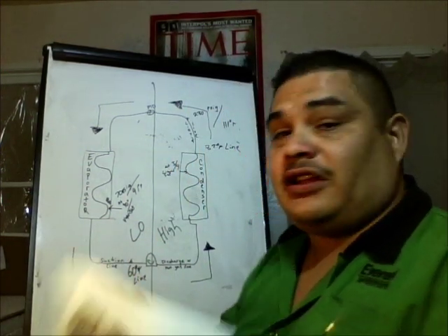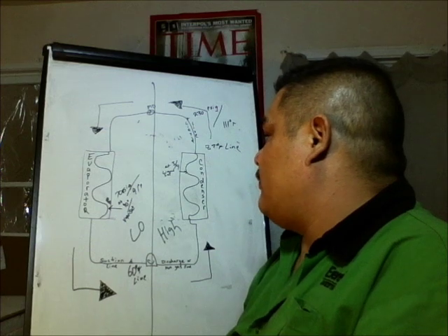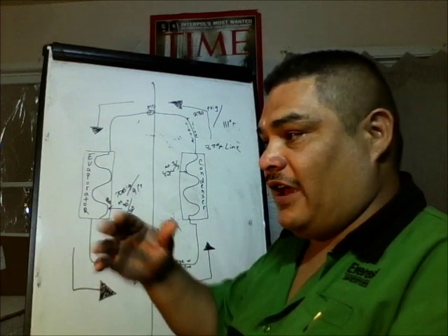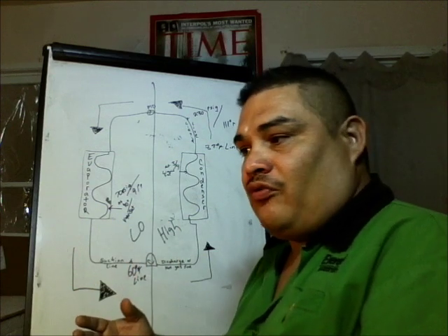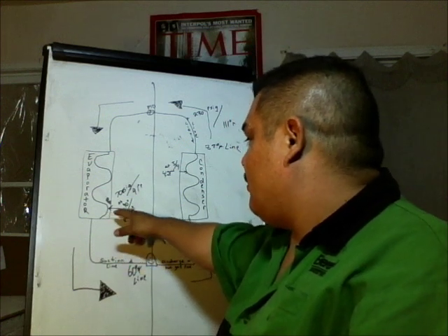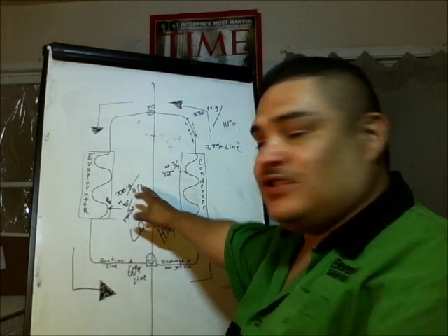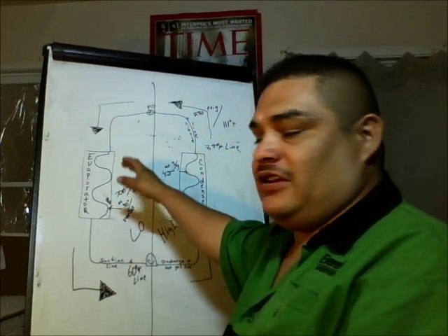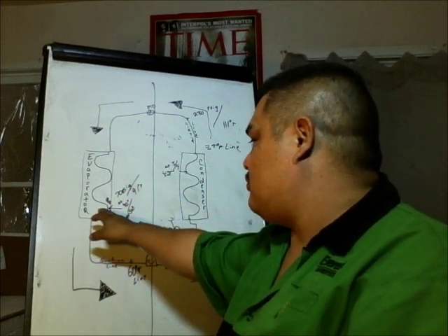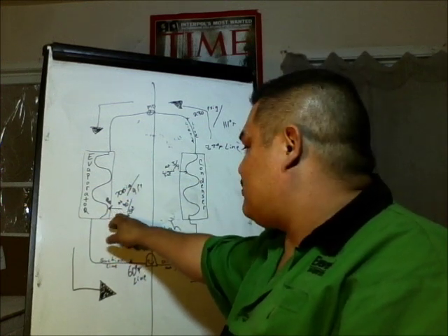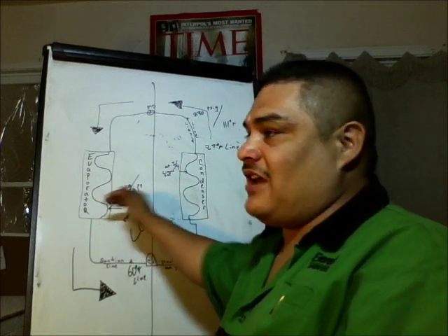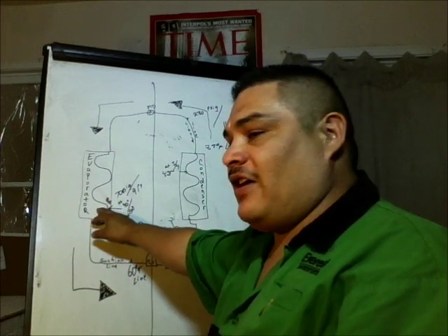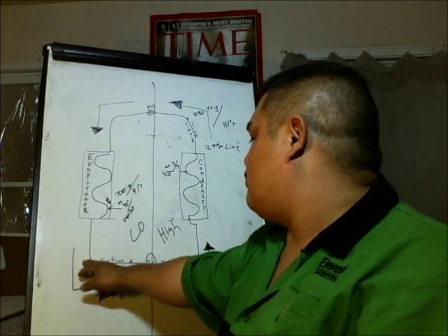Basically, to break it down as easy as possible, superheat, if you know your definition, is added heat past the point of saturation. So here in the evaporator, when you get to 90%, that's when saturation happens. That's vapor saturation, where the liquid coming in is completely turned into a gas. It happens at 90% of evaporators. So once you hit 90%, think of that as kind of a stop sign, and that's where the door opens into superheat. It starts in the evaporator at 90%, and you begin to enter into superheat.